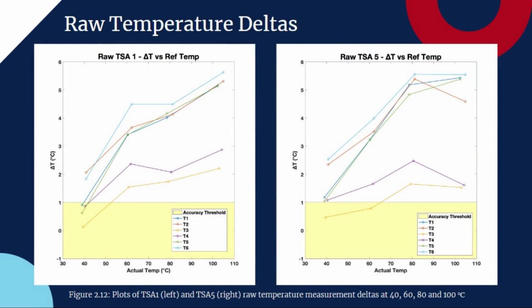In doing so, we observed the following temperature differences between the measured temperatures and the actual temperatures for each sensor on each thermistor sensor assembly. As expected, but marginally higher, because of mechanical issues related to thermal expansion of different materials, we observed that the performance not only degraded as the applied temperature increased, but there are also significant discrepancies between sensors within the same assembly.